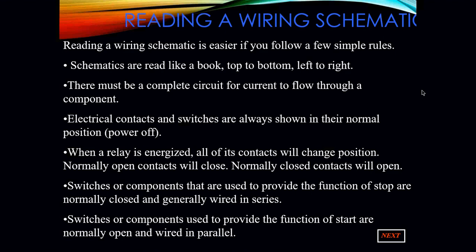Switches or components used to provide the function of starting are going to be normally open and are going to be wired in parallel of that circuit. Remember when we are always looking at a wiring diagram, all of our loads, any power consuming device, is going to be wired in parallel because that load needs to receive the full source voltage that we are applying to that circuit in order for it to work properly.